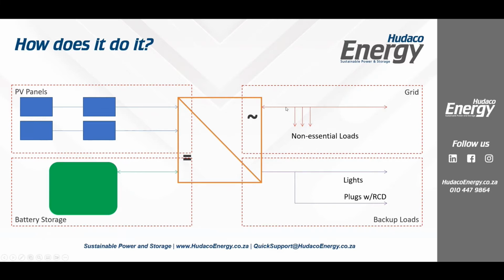So here we've got a bidirectional port from the grid. We have a voltage sensor right here, so we detect voltage over here. So long as we have voltage here, in other words, so long as the grid is present and this voltage is in range, according to NRS 230 plus or minus 10%, this port remains active and bidirectional.